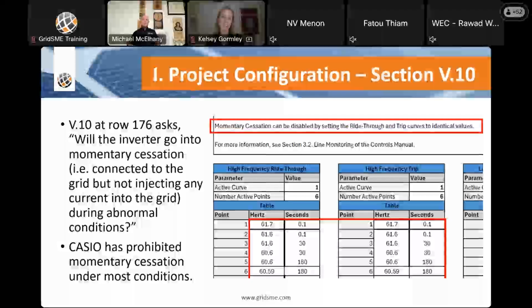So how do we determine that? Again, I showed you the slide of 12 different inverter manufacturers. Every one of them is different. The example I'm showing here, in their inverter settings report, has this top red box: momentary cessation can be disabled if you set the ride-through and trip curves to identical values. On the left you have the ride-through, and then the trip side, and you have to understand there is a frequency component and a voltage component, but in these tables I only showed the frequency and I should have shown the voltage as well. But as long as everything in the left-hand table matches everything in the right-hand table, that means momentary cessation is disabled.